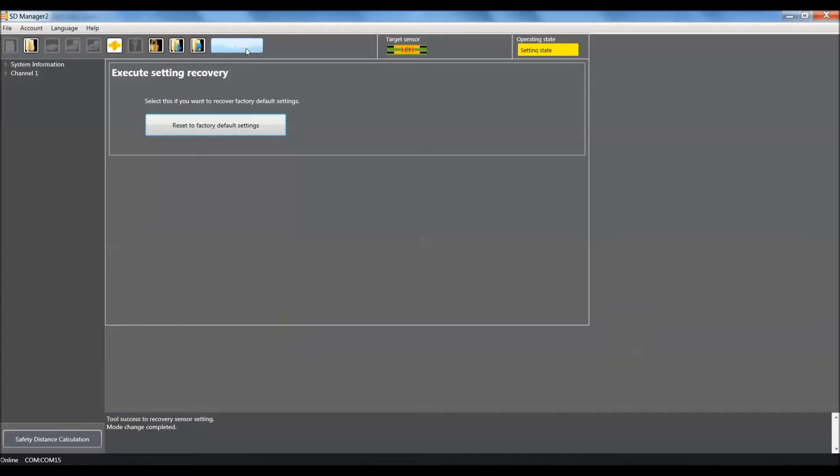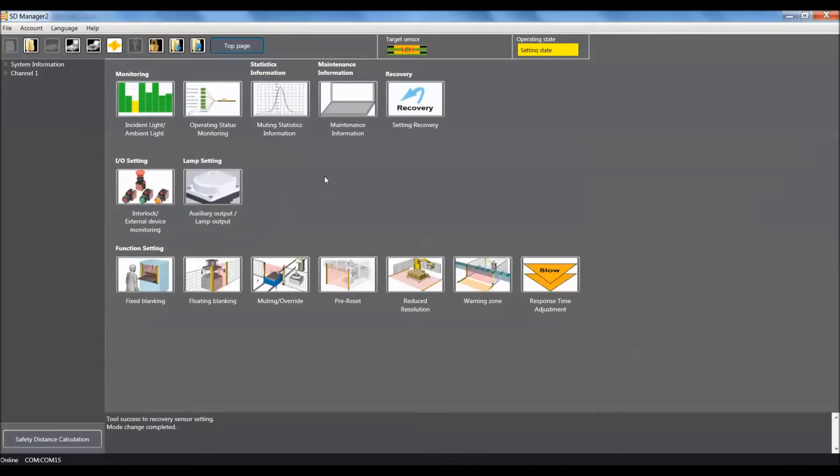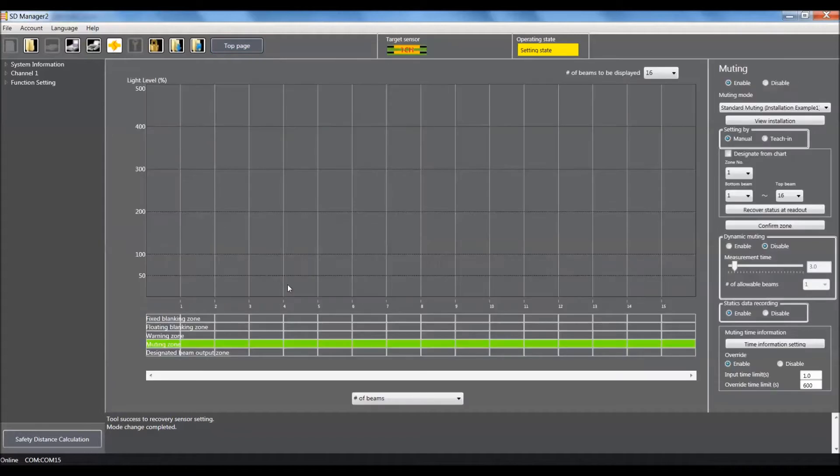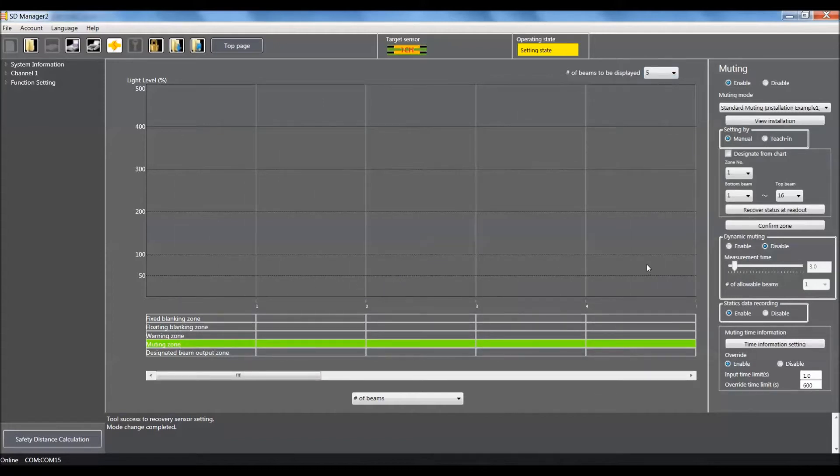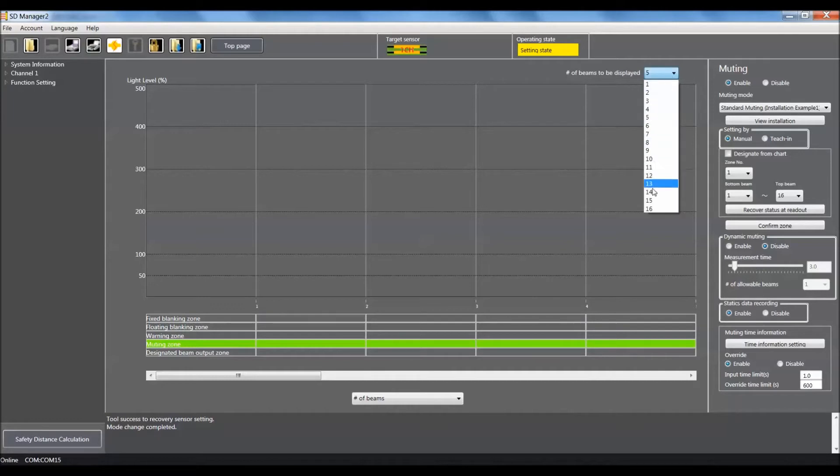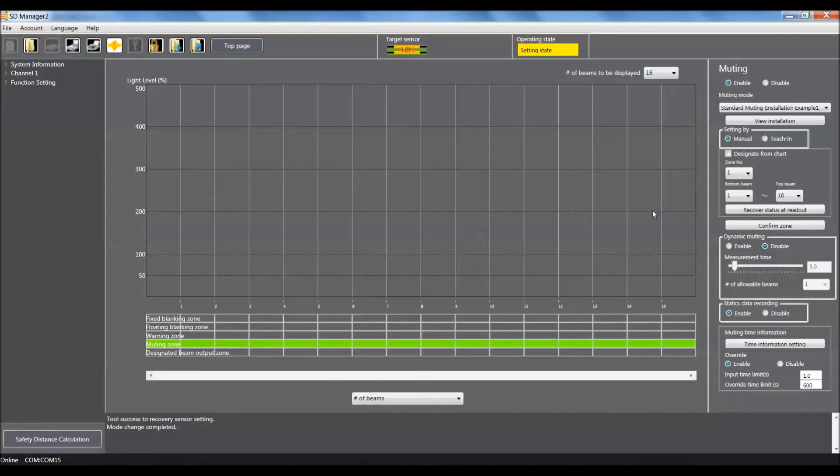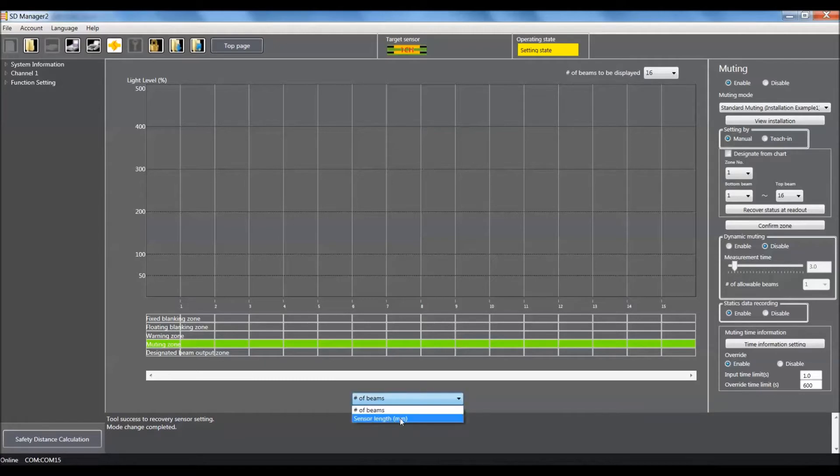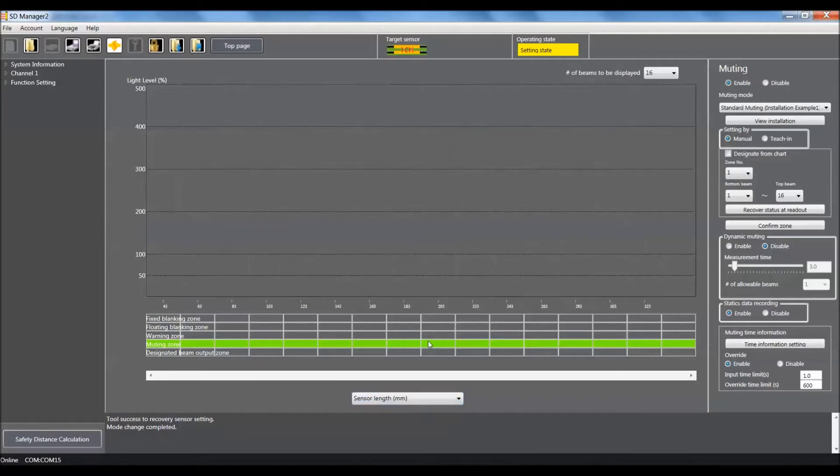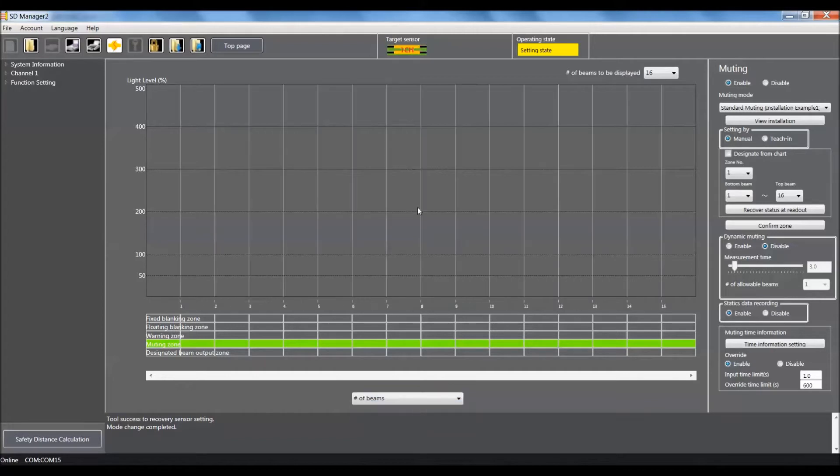Now we'll go back to the top of the page and come down to muting slash override. Within this screen, we have the ability to zoom in on any particular beams or zoom back out. We can also select or change the axis to number of beams or sensor length in millimeters. In this case, I'll just keep it in number of beams.